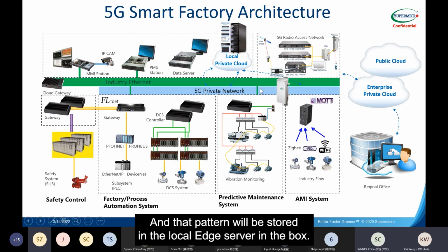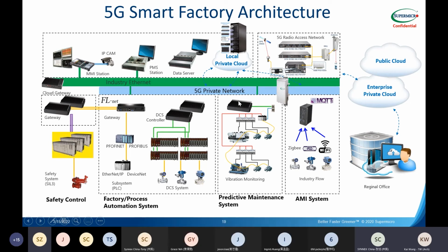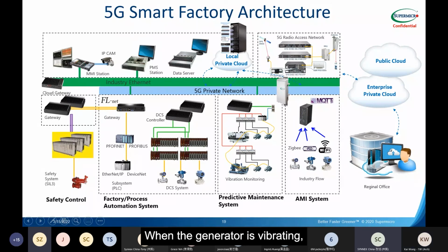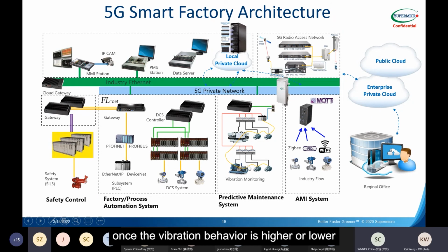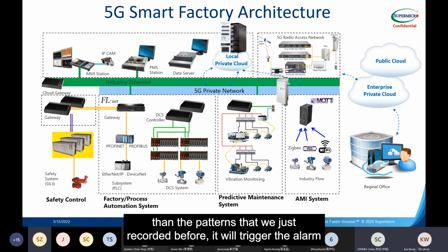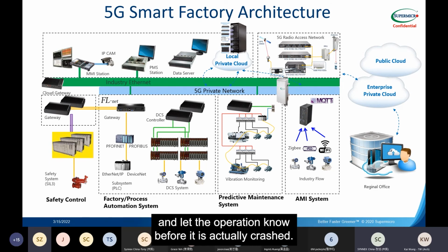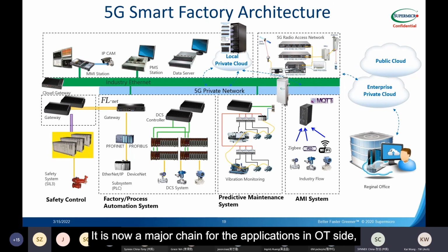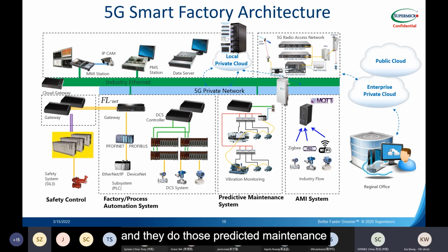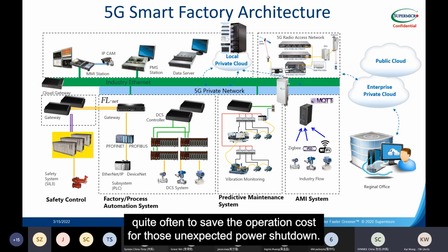That pattern will be stored in the local edge server, in the Phoenix box. So when the generator is vibrating, once the vibration behavior is higher or lower than the patterns we recorded before, it will trigger the alarm and let the operation know before it actually crashes. So this is now a major trend for applications on the OT side, and they do predictive maintenance quite often to save operation costs from unexpected power shutdowns.